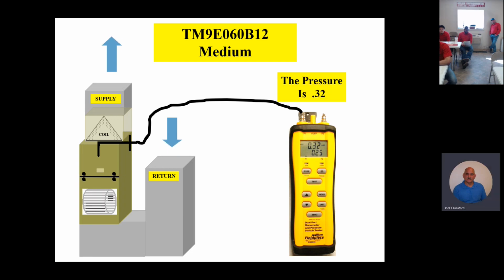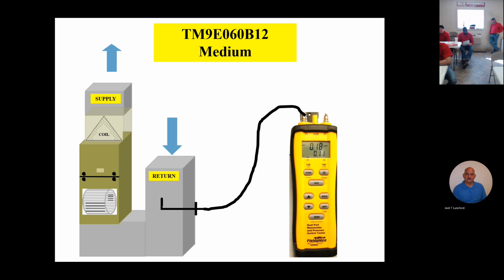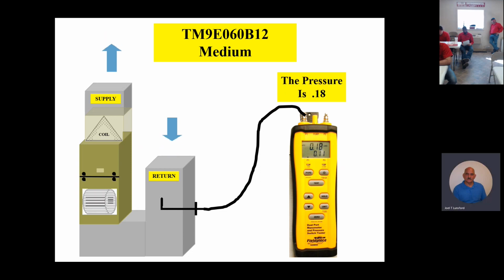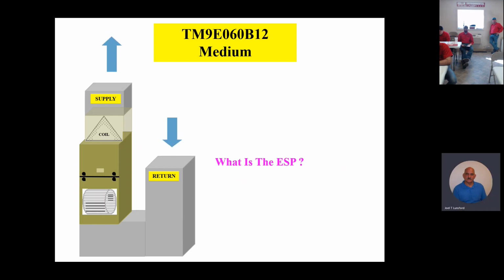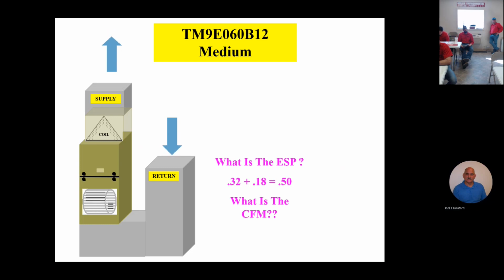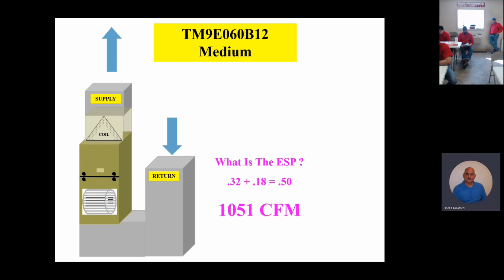So our static pressure on the supply side is a 0.32 on it. This is a TM9E060B12 medium speed tap. 0.32, just write that down and remember it. On the return, it's a 0.18 for a total of 0.5. And so what's the CFM on that TME 60 medium speed tap at 0.5 inch of static? What's our CFM? 1050. Okay, good, excellent. All right. Good. Any questions on that?